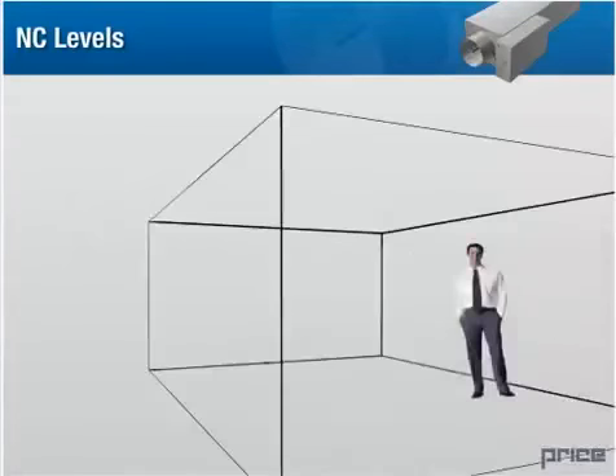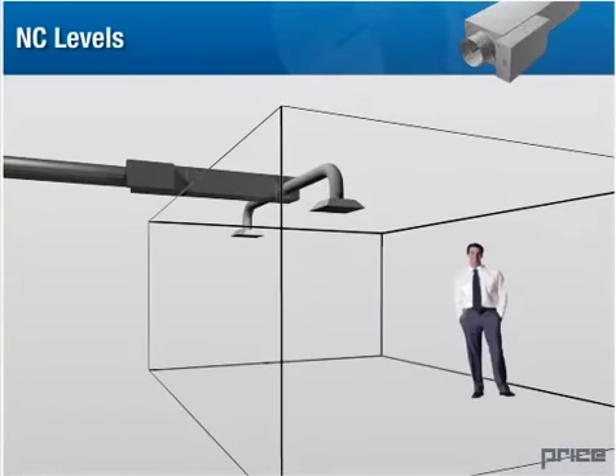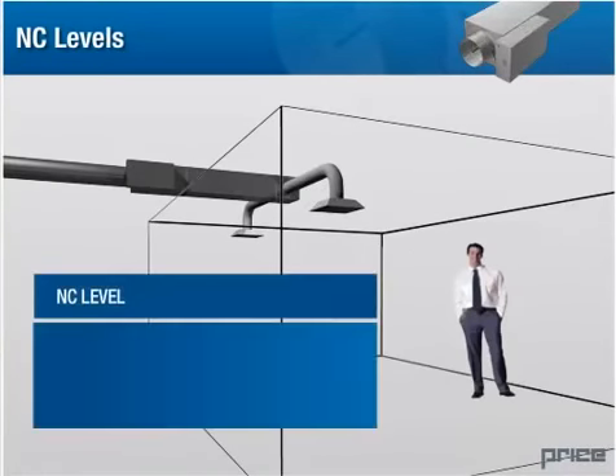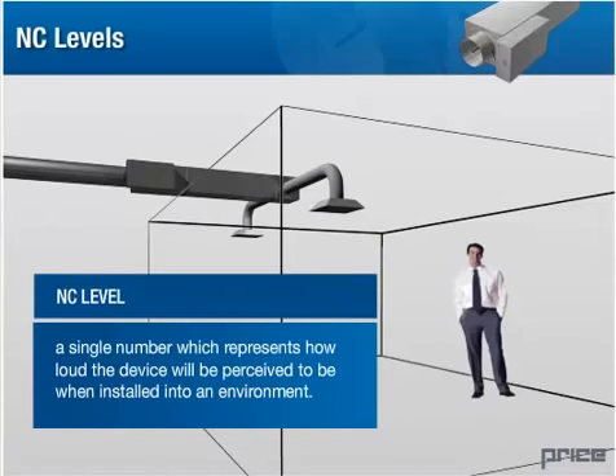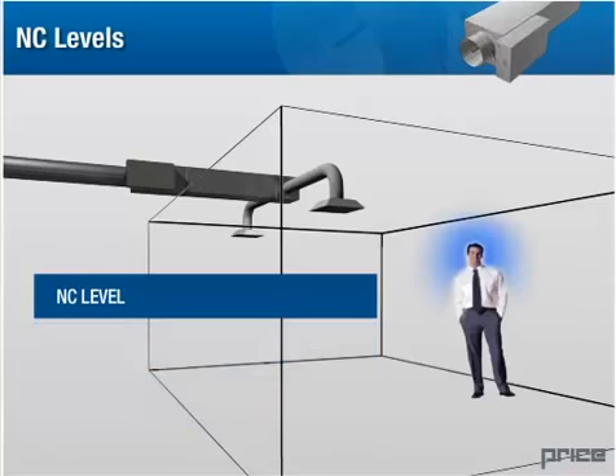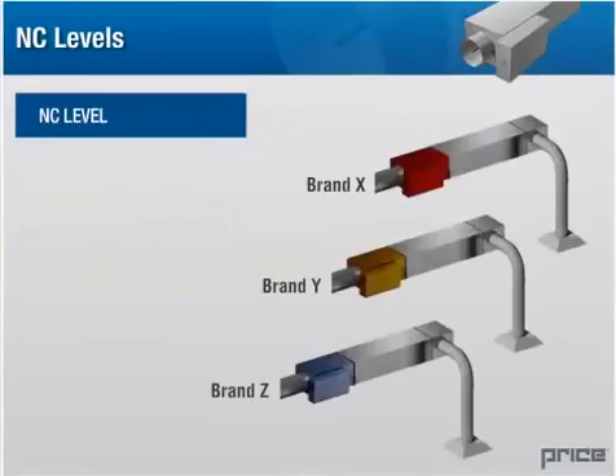Another way that the data is provided by the manufacturers is as an NC level for the terminal unit. An NC level is a single number which represents how loud the device will be perceived to be when installed into an environment. It takes into account the human response to different frequencies, as well as the path that the noise takes to get to the observer. The NC level gives designers a good idea of the actual noise level that may be experienced in a room and a basis of comparison between different products.